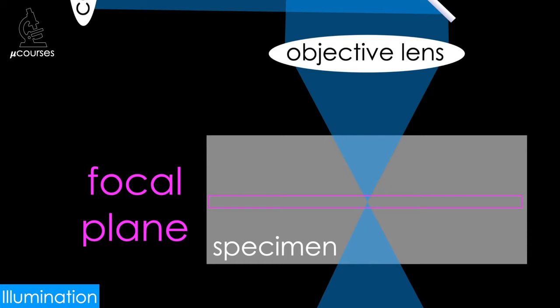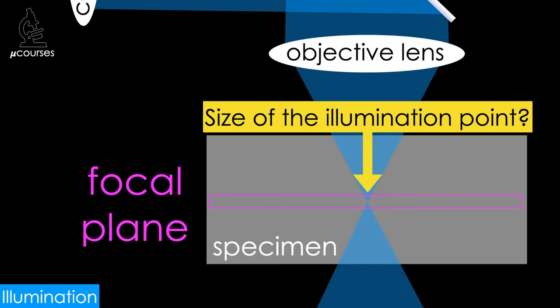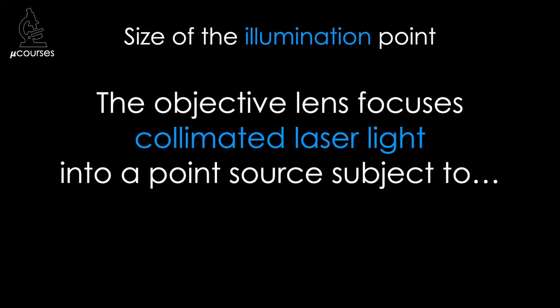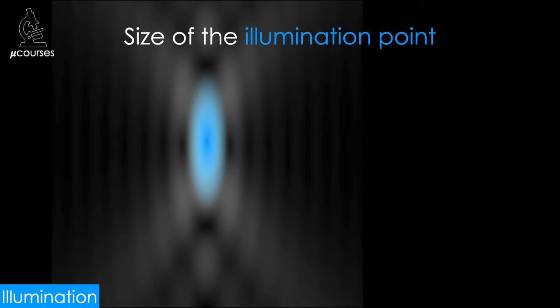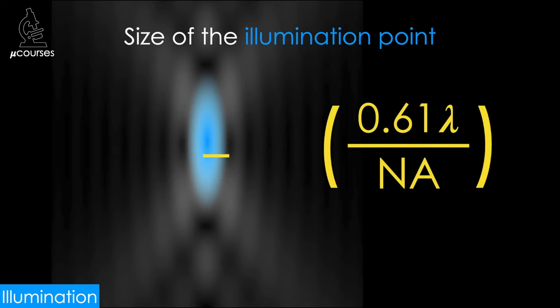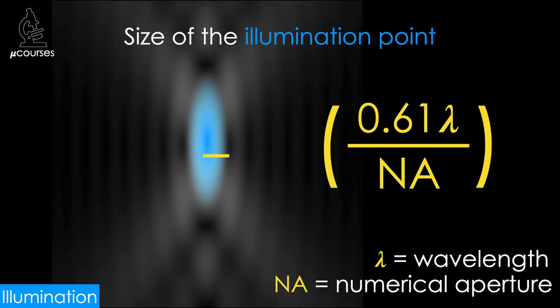So the light is focused into a point. You might be wondering: what is the size of the illumination point? The objective lens focuses collimated laser light into a point source that's subject to the point spread function. The expected size of the illumination point can therefore be calculated using the resolution equation. The resolution equation gives us the expected radius of the point source, which is equal to 0.61 times the wavelength of light divided by the numerical aperture of the objective lens. We can double this number to get the diameter of the point source.